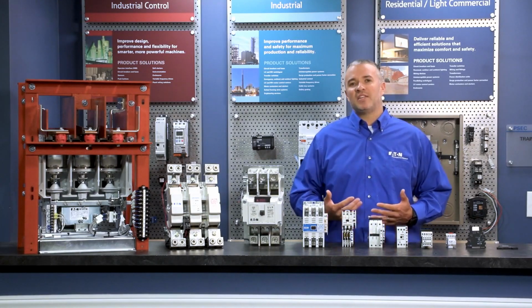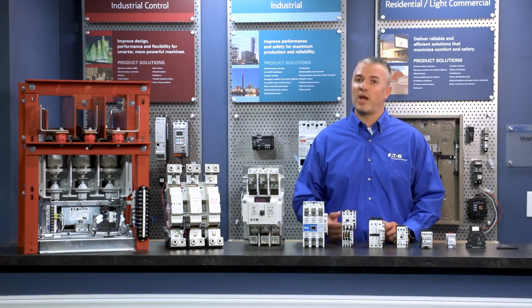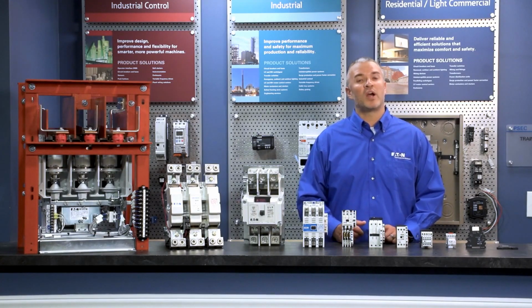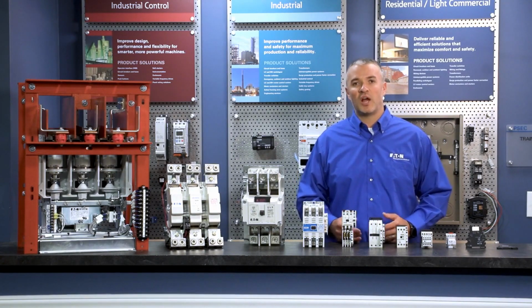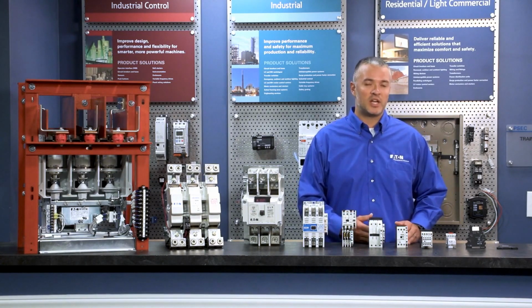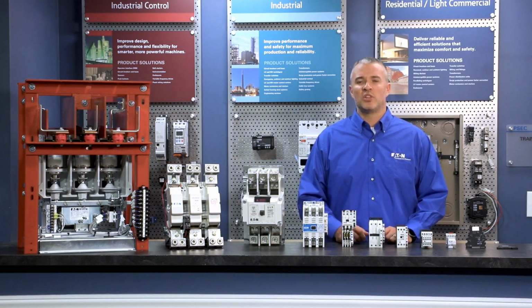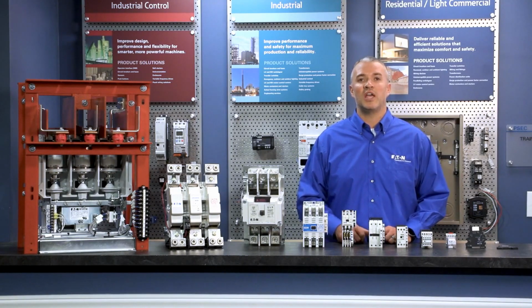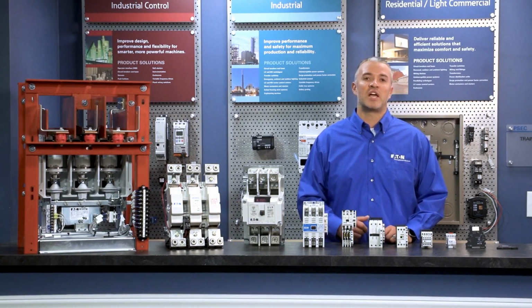So what's different about IEC? IEC allows the engineer to choose a product not just on its ratings, but also its duty cycle. That means IEC products require more front-end engineering. For example, you have to know the duty cycle, or how many times you are going to operate the contactor and how often. And unlike NEMA, which only requires that you know the motor horsepower, IEC requires that you know its full load current and information about the load that is connecting to the motor. This will be a deciding factor in determining if you can use a smaller size contactor.